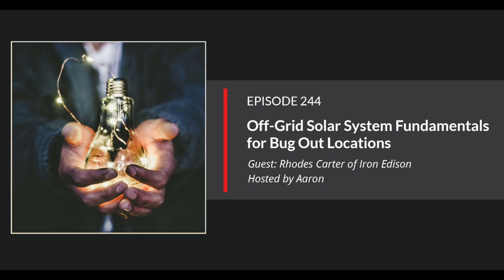Backing up a little bit, there's some lead acid batteries that are flooded batteries, kind of like the old car batteries in the 1970s and 80s, where you had to check the water levels and top them off periodically. Some of the lead acid batteries being used today are flooded, and they do require some maintenance like that. Others are sealed, and they don't. So besides sealed and maintenance-free and also just smaller physical size, those are the main characteristics of lithium. Life expectancy is quite a bit longer as well. In the off-grid, just solar storage world, you can see anywhere from 10 to 20 plus years life expectancy from a lithium battery bank, which is significantly better than the 5-ish years with the lead acids.